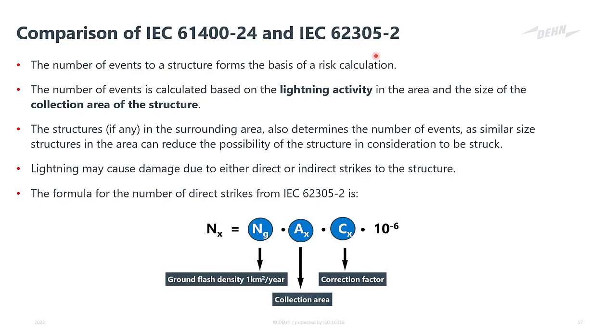Now, as I said, the aim is to calculate the number of events to a structure, or the number of strikes to a structure, and this forms the basis of any risk calculation. If we know how many times we will get struck, we can also calculate the probability that we will have damage and what the amounts of damage would be. Now, the number of events is calculated based on the lightning activity in the area, known as flash density, and the size of the collection area of the structure. So flash density is a measuring technique or method for lightning activity in an area, and it's measured in the number of lightning strikes per square kilometer per annum within the area.